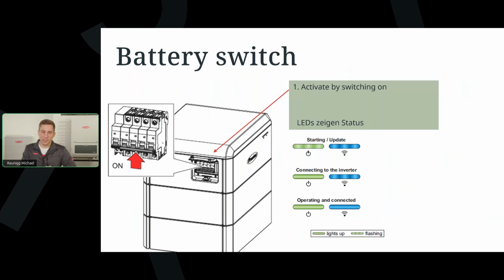To switch on the battery system, on the left-hand side of the battery system, we have our DC main switch. This is placed with a little cover. You can just come to the cover, put the battery to on, and make sure that the battery is then activated. On the front side, you then have two battery status indicators. One is for the actual status of the battery, and the other is for the connection for the data communication to the inverter. So as soon as you put on the battery, the LEDs will go live and will show you if there is a communication to the inverter and if the battery system is working or not.